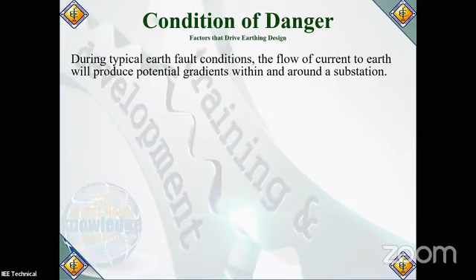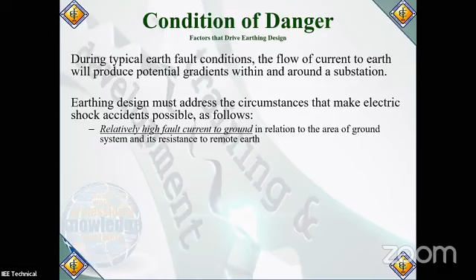Earthing design must address the circumstances that make electric shock accidents possible, as follows: relatively high fault current to ground in relation to the area of the ground system, and its resistance to remote earth. Number 2, soil resistivity and distribution of ground currents such that high potential gradients may occur at points on the earth's surface. And of course, the presence of an individual at such point, time and position that the body is bridging two points of high potential difference, and the absence of sufficient contact resistance or other series resistance to limit current through the body to a safe value under the above circumstances.